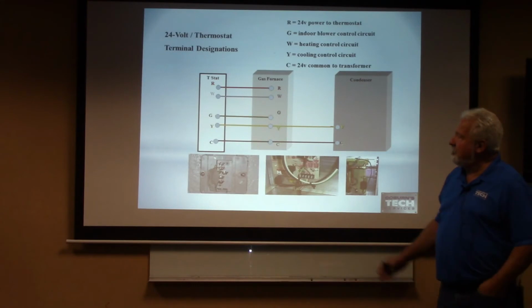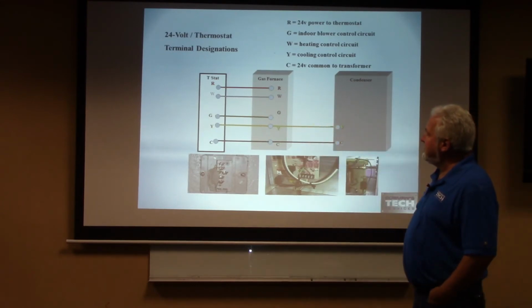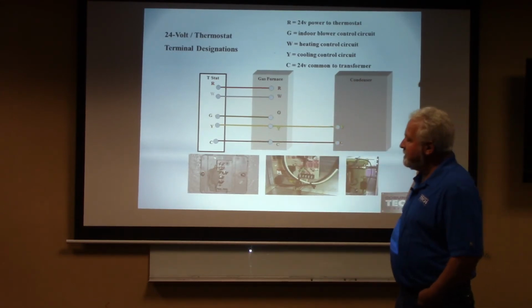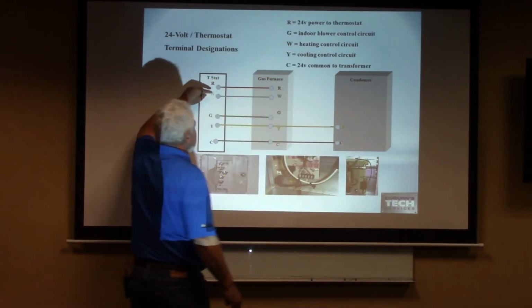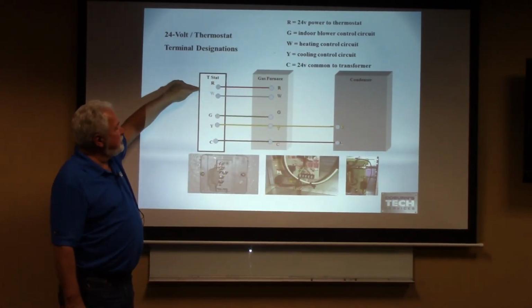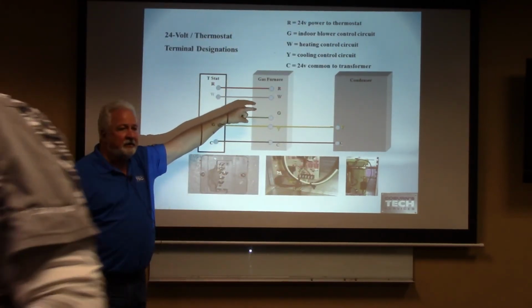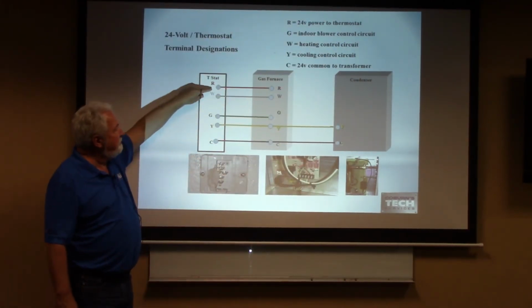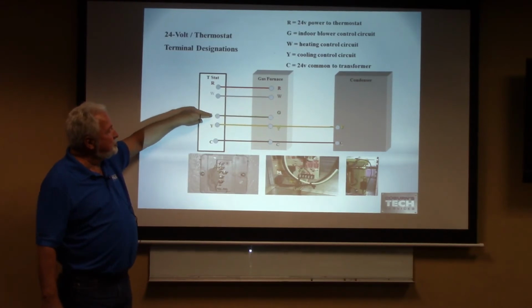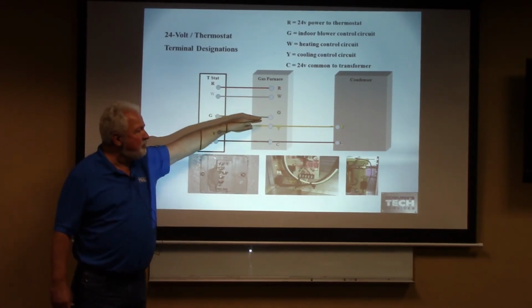So if we have our thermostat, our gas furnace, and our condenser, when I have 24-volt voltage going to my white, it's going to send that to my gas furnace and cause my furnace to come on. If I send that R to my G, it's going to turn on my blower motor.